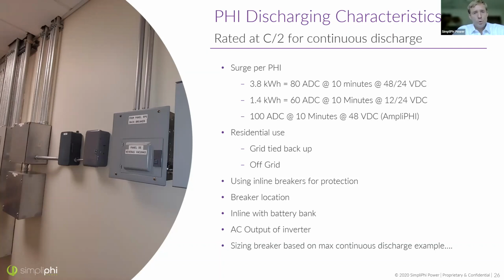Okay, so you can use inline breakers for protection. However, some people will come to us and say, hey, I'm putting in a 12 kilowatt inverter, but I know my customers are not going to be drawing at 12 kilowatts. They're only going to be drawing at 7 kilowatts. And so I want to install just 4 batteries here. So I can put a battery bank with 4 batteries in. And even though I know these batteries are not capable of a continuous discharge rate at 12 kilowatts, can I just put fuses in, inline breakers in, to prevent the system from drawing any faster than the batteries should?